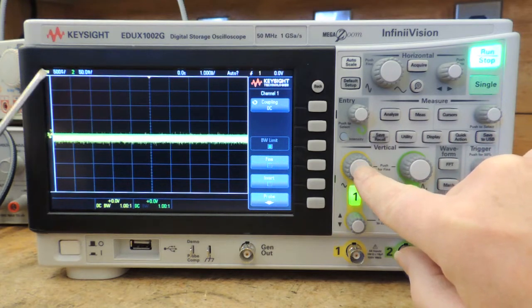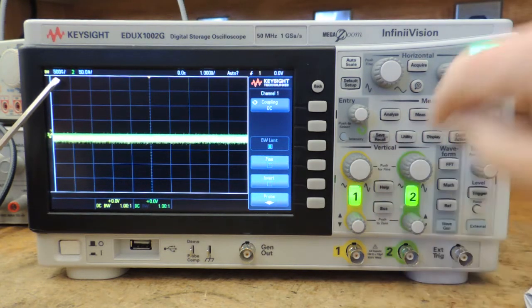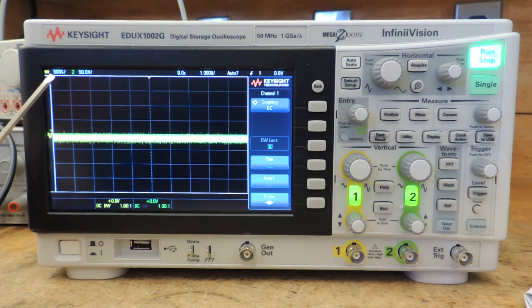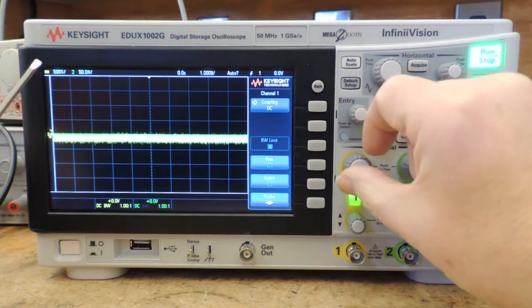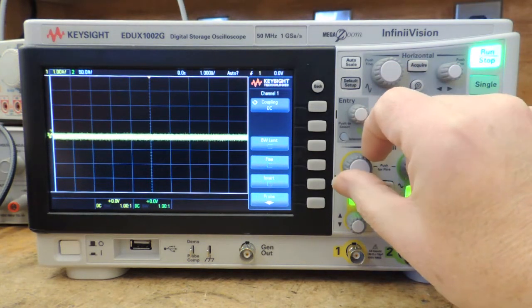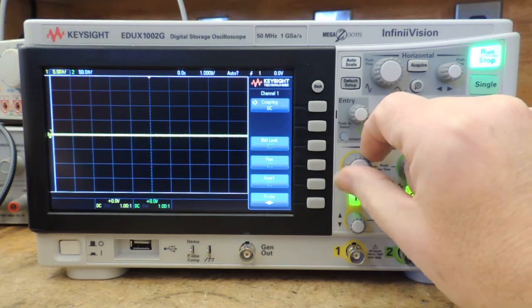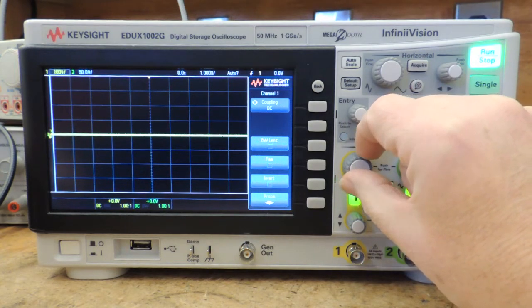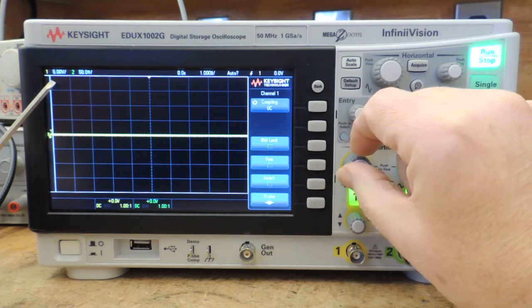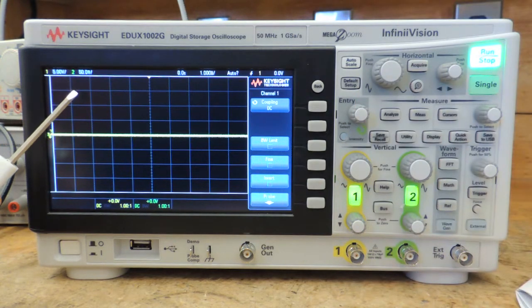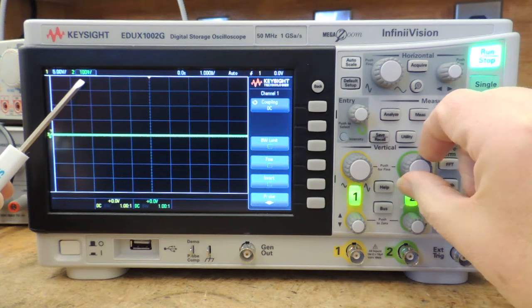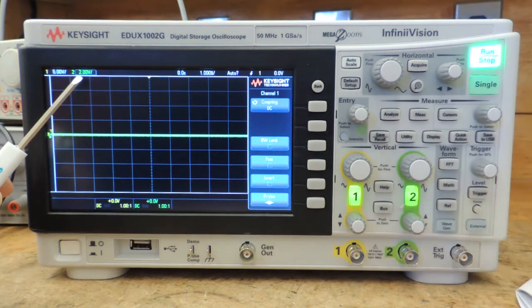So you can see right now they're at 500 millivolts, and the lab wants us to set it for 5 volts per division. So adjusting the volts per division knob for channel 1, I'm going to select 5 volts per division. Now for channel 2, they want us to put the scale on 2 volts per division. So rotating the knob counterclockwise in my case, I'm going to set it up for 2 volts per division.